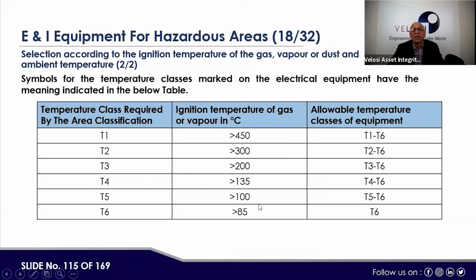T6 means the surface temperature should not exceed 85. T1 means the surface temperature should not exceed 450. And the allowed temperature class of the equipment is T1 to T6. A lower-class number cannot be used where a higher one is required: T6 equipment can be used in basically T1, but T1 cannot be used in T6 or even T2. So this is the range; the equipment should not be creating heat which can create ignition in that particular area.